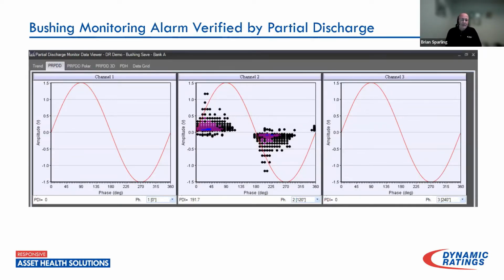That particular bushing also revealed we had inputs for partial discharge signals. That bushing, the phase B, channel 2 was showing partial discharge inside the bushing as well. So that was contributing to the failure condition, and one more reason for them to hurry up and get it replaced.